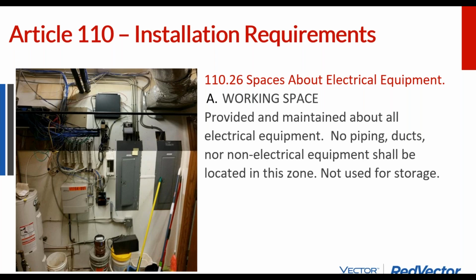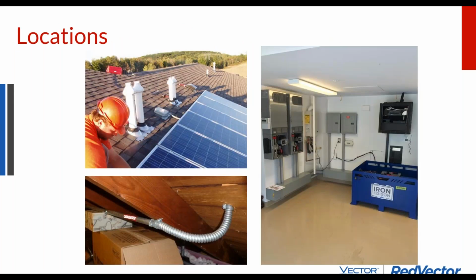And I guess we're assuming that all that security stuff is low voltage. Really the only code violation that the inspector will have the most problem with is the storage stuff in front of the service panel. So that's when we talk about dedicated spacing, it's not just keeping gas out of electrical or plumbing out of electrical. It's also dedicated where you can't have other stuff being stored there.